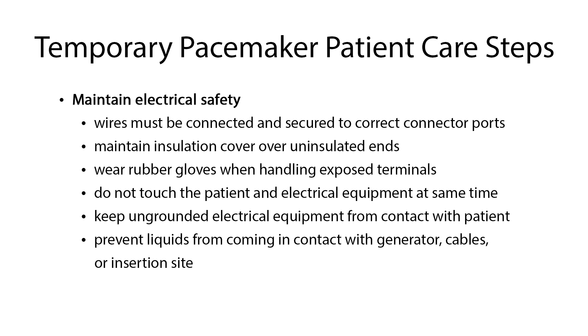Keep the insulation cover over the uninsulated ends. Wear rubber gloves when handling the exposed terminals. Do not touch the patient and electrical equipment at the same time. Keep ungrounded electrical equipment from contact with the patient. And prevent liquids from coming in contact with the generator, cables, or insertion site.